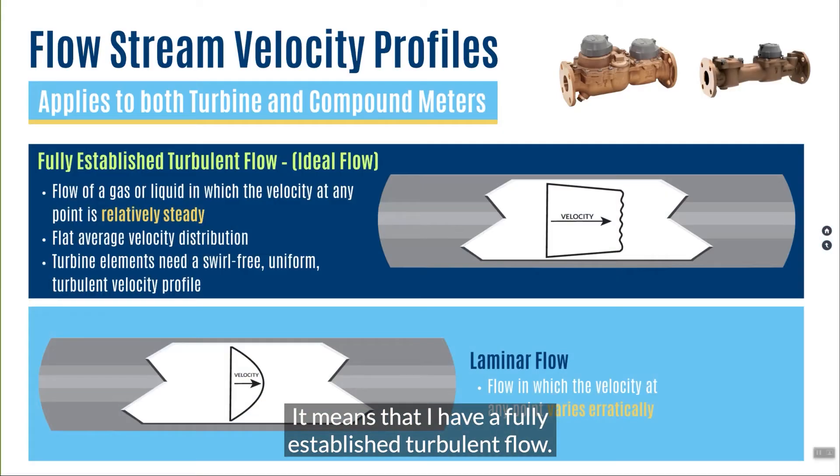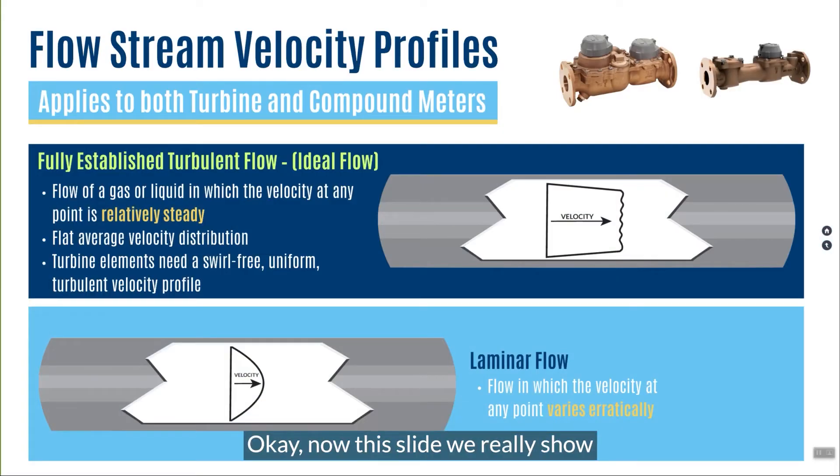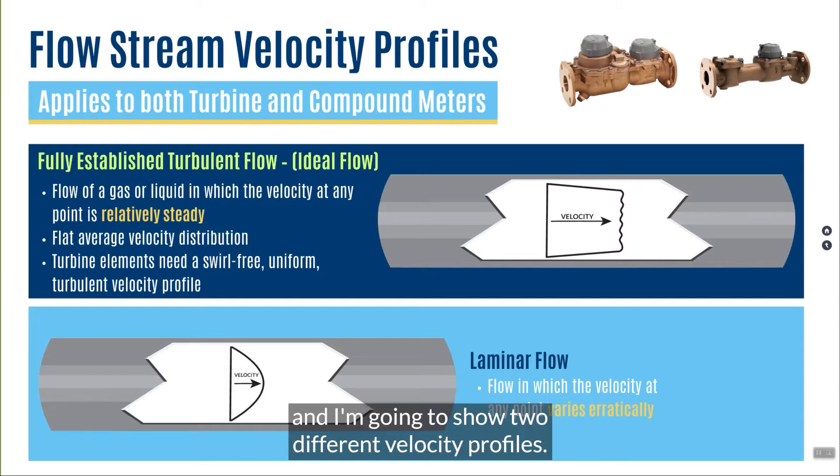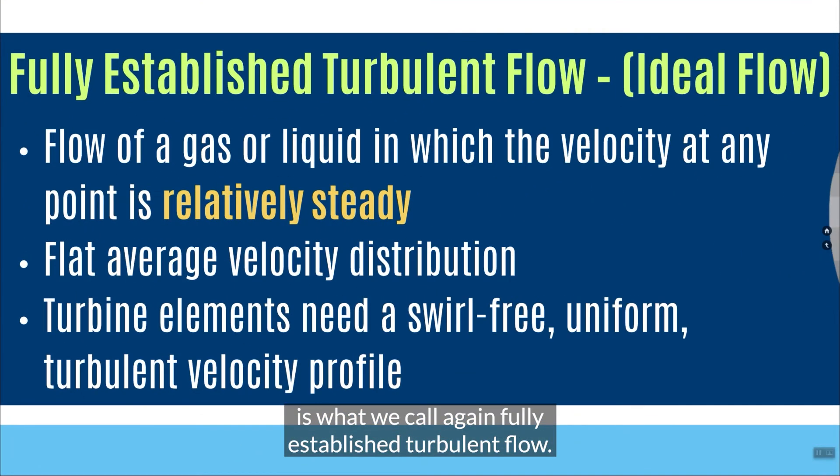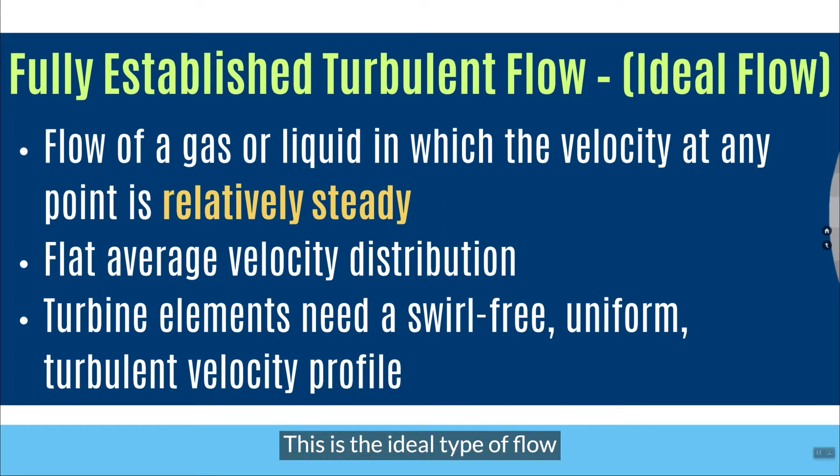What do I mean by that? It means that I have a fully established turbulent flow. Now, this slide, we really show two different pipes here, and I'm going to show two different velocity profiles. The first one that I'm going to talk about is what we call, again, fully established turbulent flow. This is the ideal type of flow for a turbine meter to operate correctly.